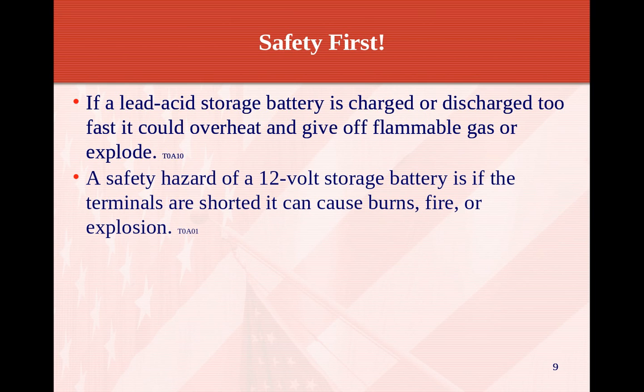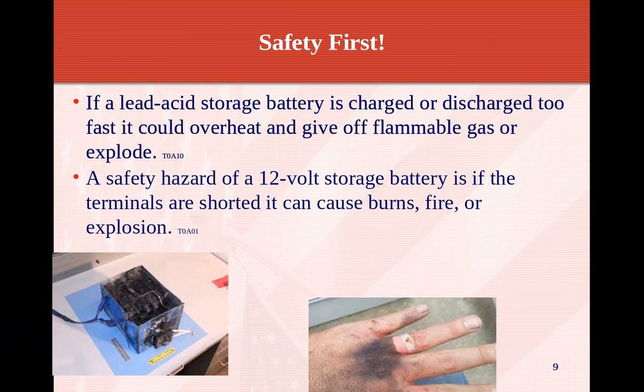A safety hazard for 12-volt storage batteries: if the terminals are shorted, it could cause burns, fires, or explosion. So you got to be real careful when working around these batteries, and you don't want to accidentally touch the two terminals together with a wrench or something metal, because it could cause hundreds of amps to flow through it, and it gets really hot and it could cause a burn, a fire, explosion, or all three.